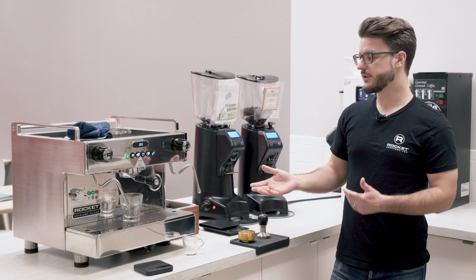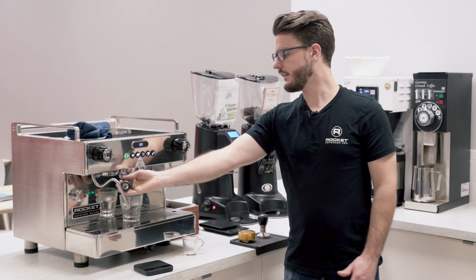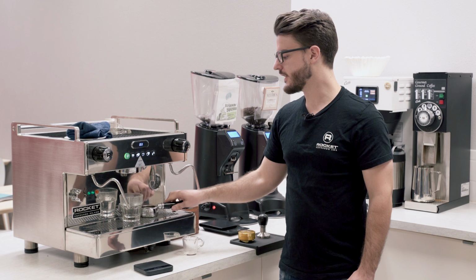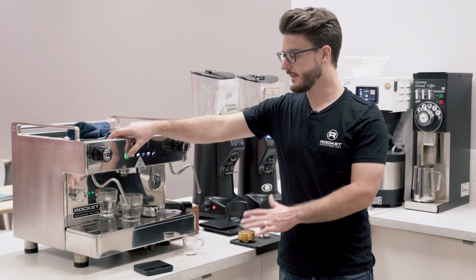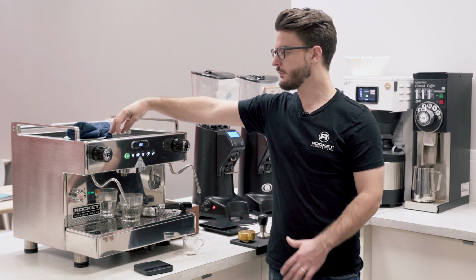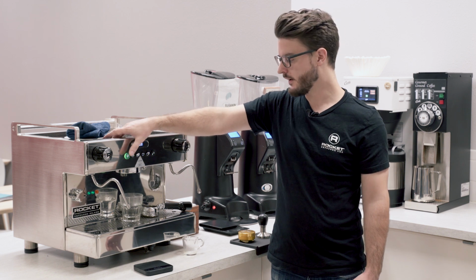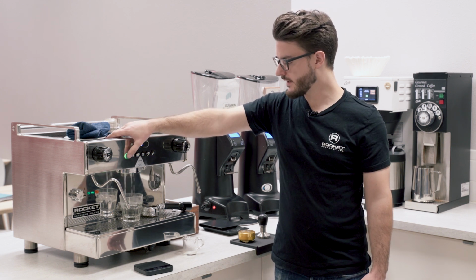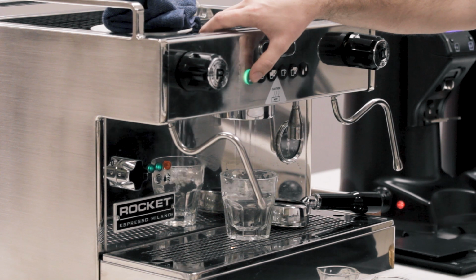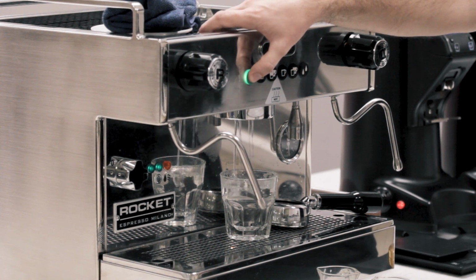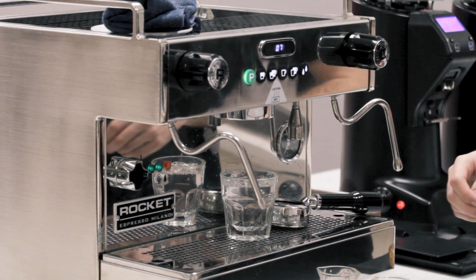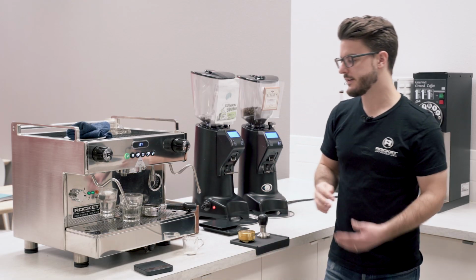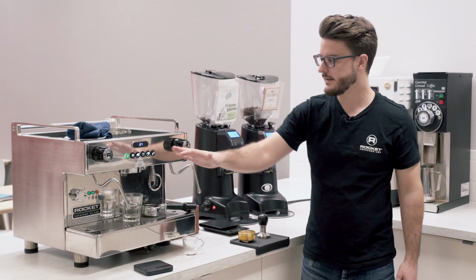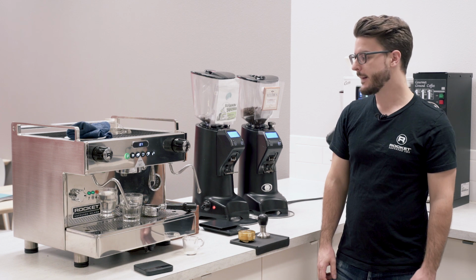So it's a pretty simple machine overall. Like I mentioned, it is a heat exchanger, so this has been sitting for a little bit, so there is some superheated water in that heat exchanger. I can purge that out until I no longer hear that crackling, and then once I stop it, I'm pretty positive that's in a good range. That was about a 6 to 7 second purge for that.